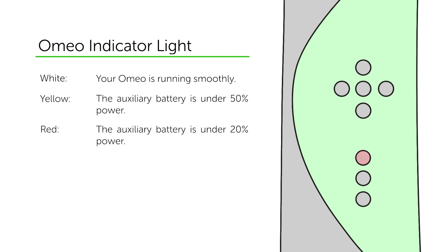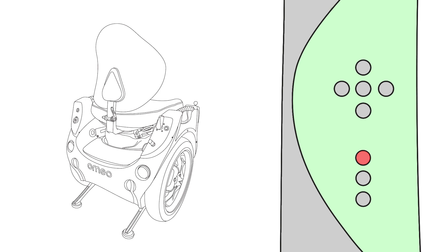If the light continuously pulses red, this means the auxiliary battery in your Omeo is under 20% battery power. During this time, if you need to raise your machine's legs, you will need to push and hold the leg raise button for 7 seconds.